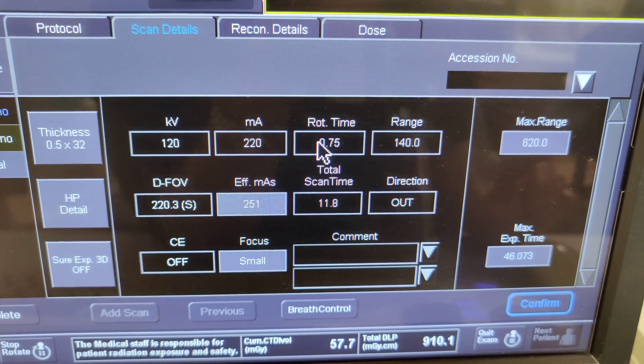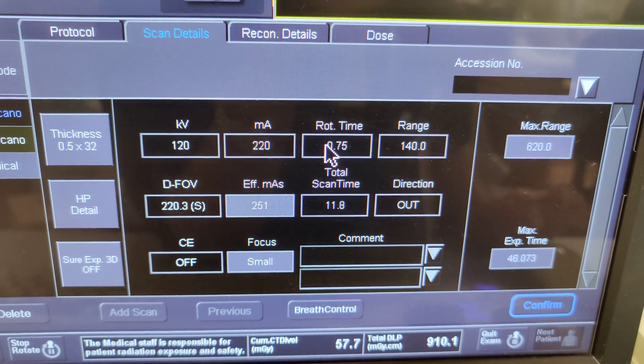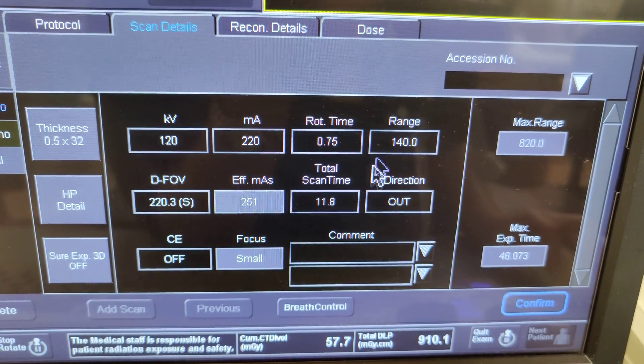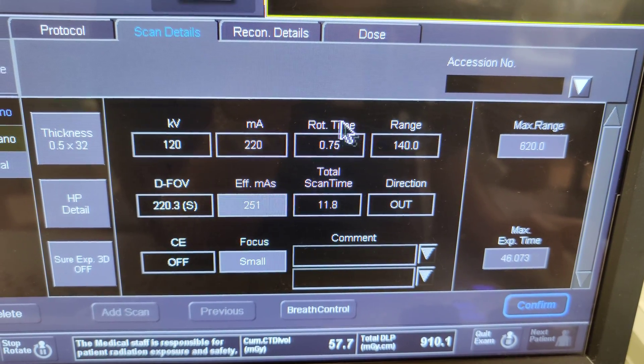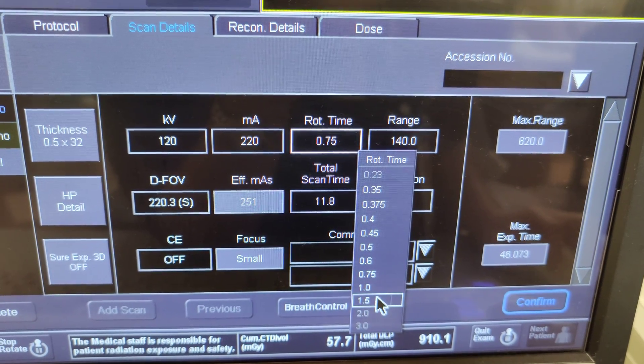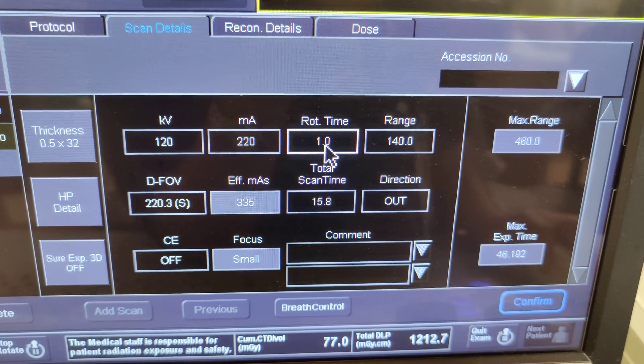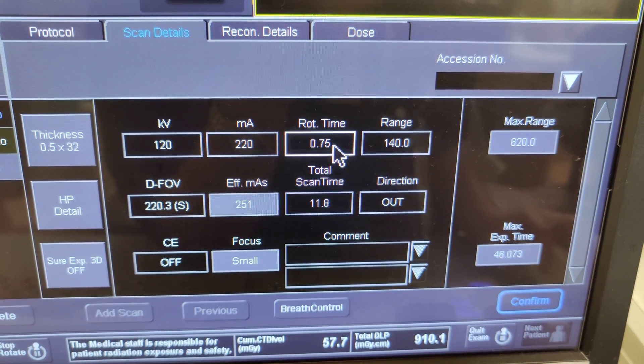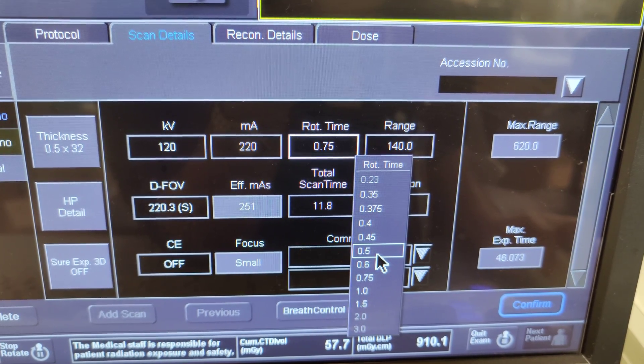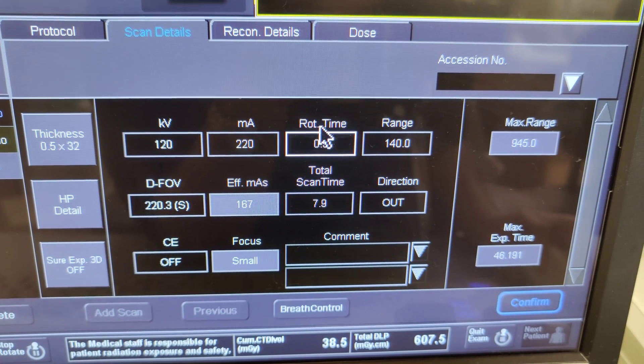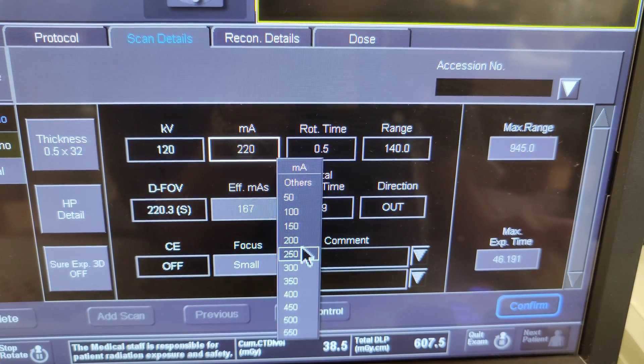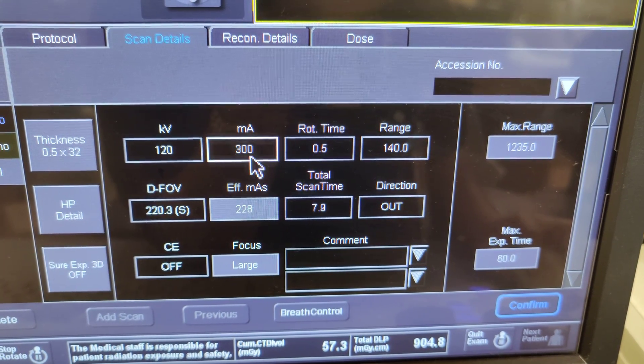Rotation time is how quickly the tube is turning in the gantry. It's going to rotate and take 0.75 seconds to go around — that's what rotation time means. If it's going to go faster, that means it's going to be a lower number, because one second is here and everything below is less than one second. Half a second means your effective mAs has changed, so you have to compensate with the MA to get back near that target point.